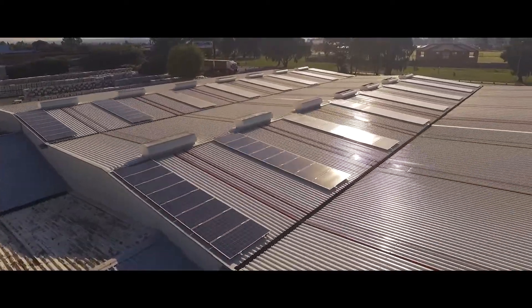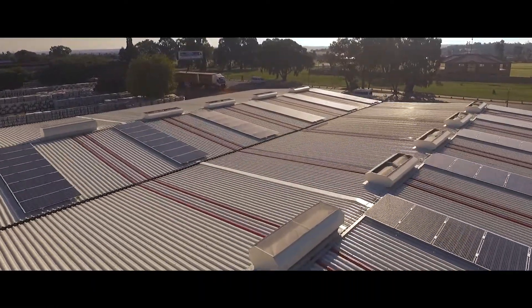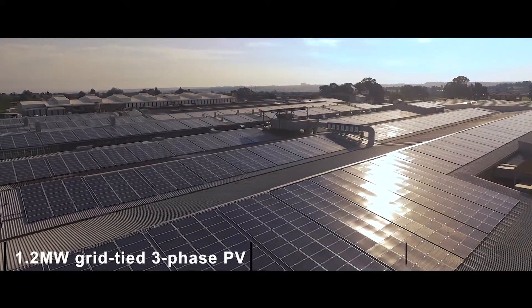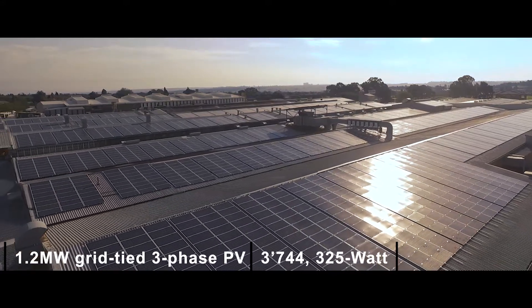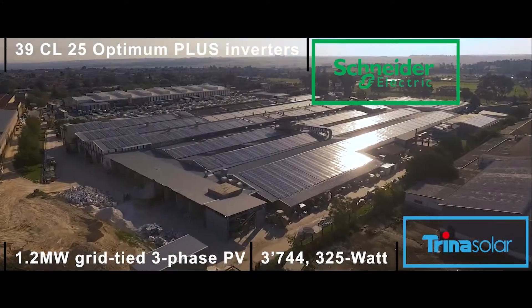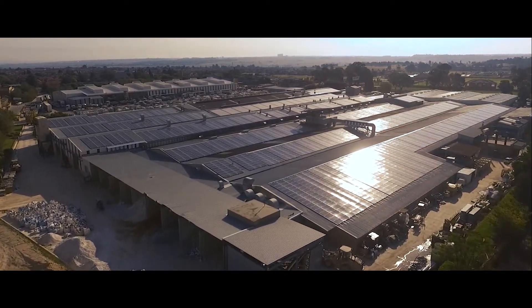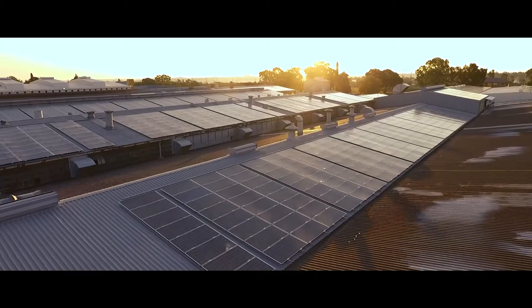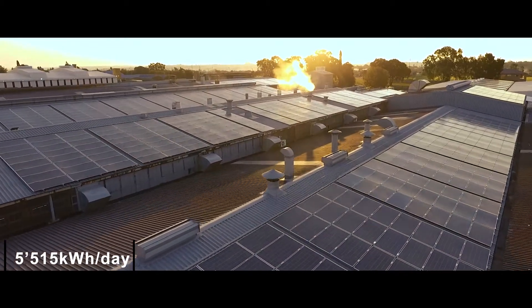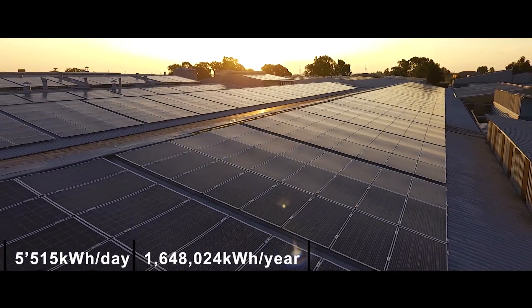Installation commenced in October 2017. We installed all the roof sub-structures, cable racks, inverters, DC strings and lastly the PV panels. The 1.2MW grid-tied 3-phase PV system is comprised of 3,744 325W Trina solar panels, 39 Schneider Electric CL25 Optimum Plus inverters and 39 surge protection units. The system includes power factor correction and reverse power protection, and is estimated to yield 5,515 kWh of solar energy per day with a total estimated annual yield of approximately 1,648,024 kWh.